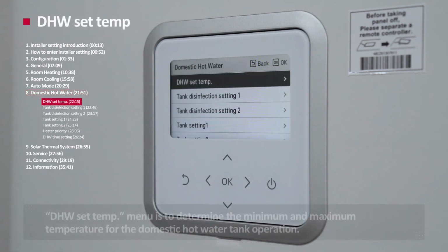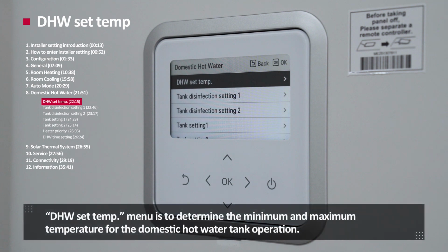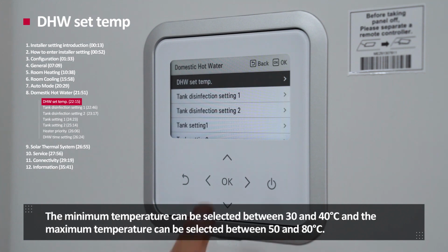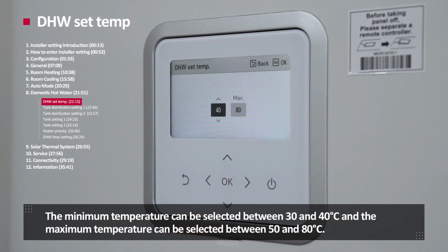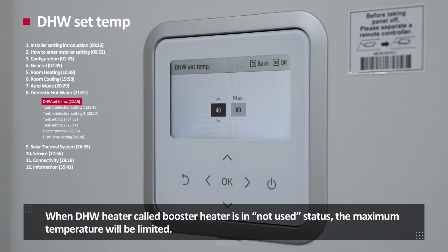DHW set temperature. DHW set temperature menu is to determine the minimum and maximum temperature for the domestic hot water tank operation. The minimum temperature can be selected between 30 and 40 degrees Celsius, and the maximum temperature can be selected between 50 and 80 degrees Celsius. When DHW heater, called booster heater, is in "not used" status, the maximum temperature will be limited.